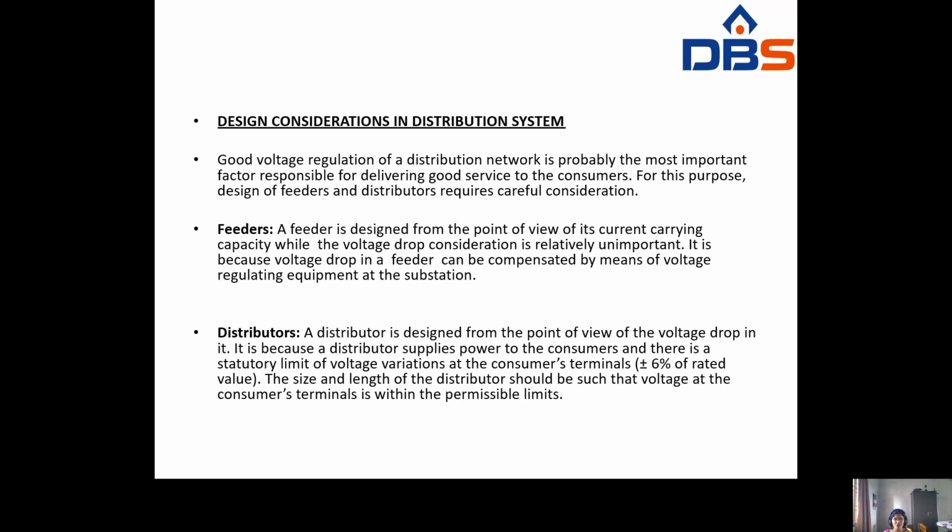Okay, next one is the distributor. A distributor is designed from the point of view of voltage drop in it. So a feeder is designed from the point of view of current carrying capacity, but the distributor is designed from the point of view of voltage drop. It is because the distributor supplies power to the consumer.